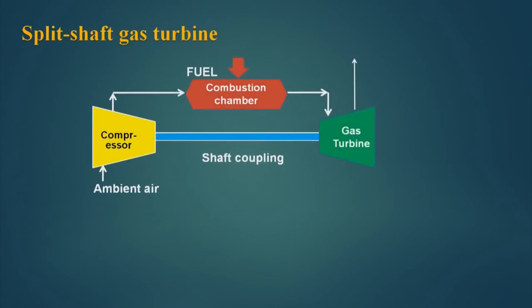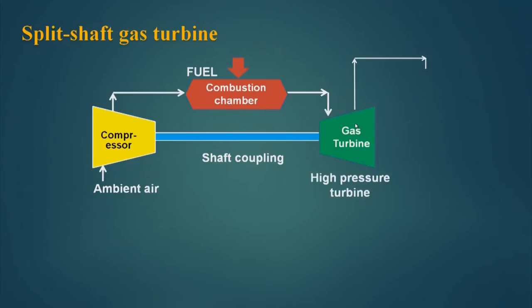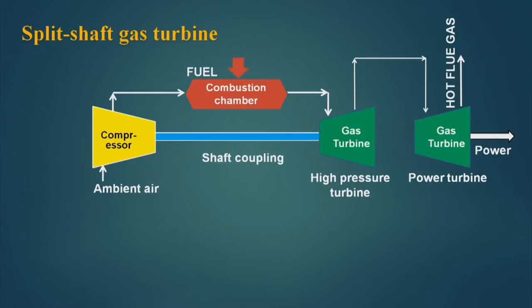Another type is the split shaft gas turbine. Here, ambient air is sucked into the compressor, compressed, and goes to the combustion chamber where fuel is added and ignited. The hot gas goes to the first gas turbine where it expands, then goes to a second gas turbine where it is further expanded and power is generated. The first turbine is exclusively used for driving the compressor. So it is broken into two parts — one gas turbine for running the compressor and the other for generation of power — and the hot flue gas which comes out can be used in the process as hot utility.